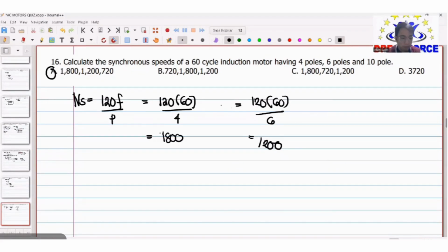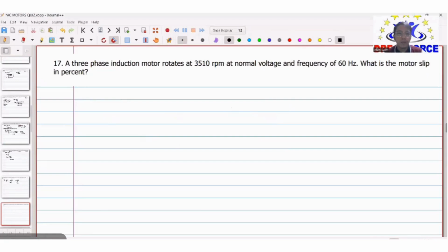Okay, next number 17. A three-phase induction motor rotates at 3,510 RPM at normal voltage and frequency of 60 Hz. What is the motor slip in percent? Okay, so itong binigay dito na 3,510, this is your NR. So again, the rotor speed is equal to 3,510 RPM. Hanapin ulit natin yung NS using your formula.